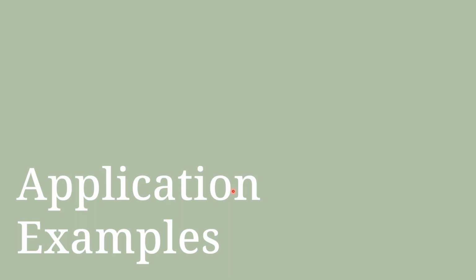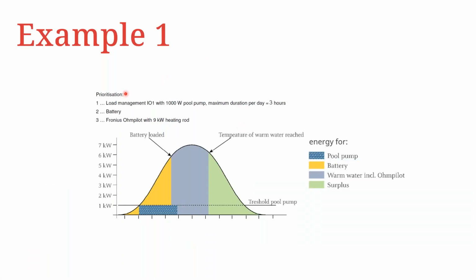We have example number 1 here. We have prioritization of 3 loads. Priority number 1 is a pool pump, which we require to operate for about 3 hours per day. After that is finished, we want to feed power to the battery. And after the battery is satisfied, we want to feed power to the Fronius Ohmpilot. You can see here that the operational threshold of the pool pump is at around 1,000 watts. Once the pool pump has finished operation, as you can see on this scale, we want the battery to start charging. And once the battery is fully charged, all the excess energy would then be transferred to the Ohmpilot for heating water.